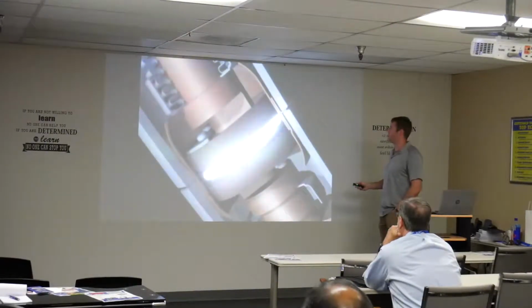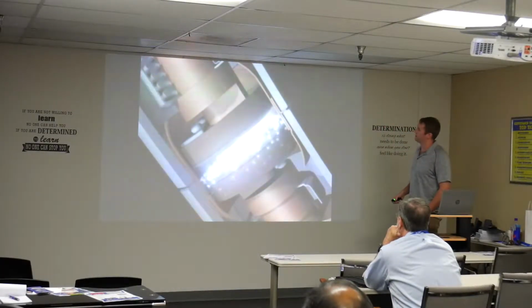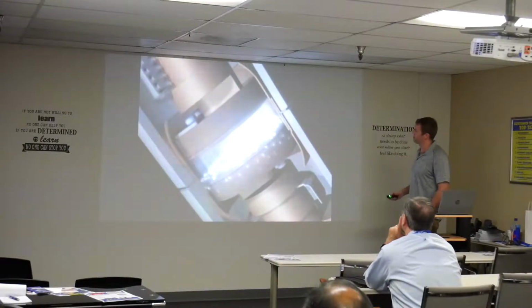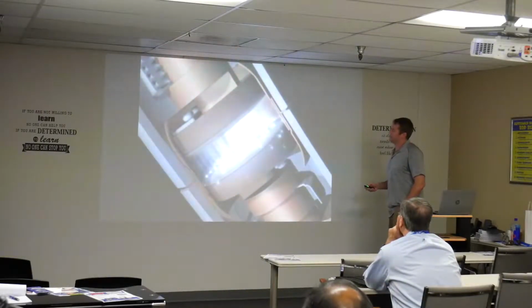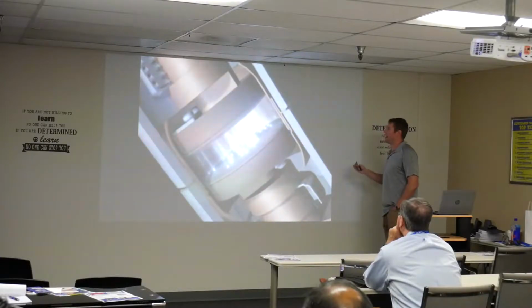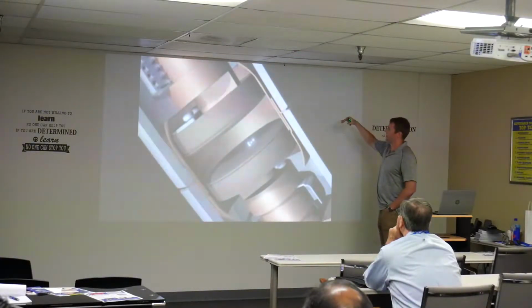It's closed, carrying load, it's opening, it's moving contacts, moving, fixed contacts stays fixed. Then it extinguishes the arc. This all happens very rapidly. All it takes is for the AC cycle to go through 0 for it to extinguish the arc.